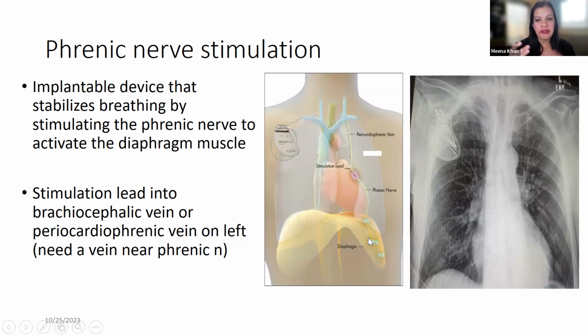And when it stimulates the hemidiaphragm, it actually engages both. We'll go into the details of how it's set, but basically we set a target rate that we want the patient to be breathing at. And if they're not at that rate, the phrenic nerve stimulator will stimulate the phrenic nerve to engage the diaphragm so they meet that target rate. And this is just an X-ray of a patient that has an implanted device.